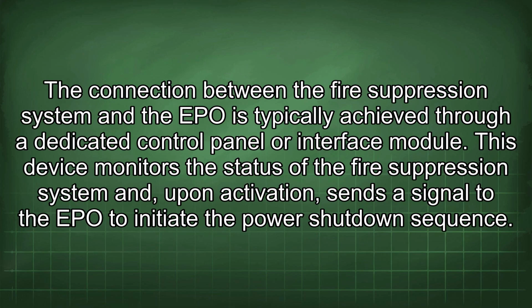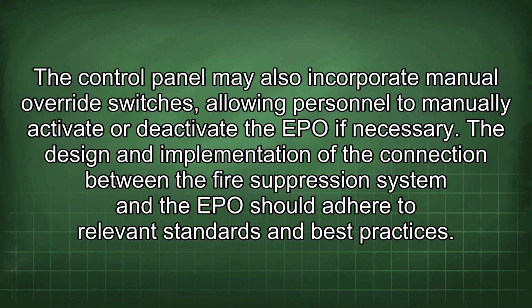The connection between the fire suppression system and the EPO is typically achieved through a dedicated control panel or interface module. This device monitors the status of the fire suppression system and, upon activation, sends a signal to the EPO to initiate the power shutdown sequence. The control panel may also incorporate manual override switches, allowing personnel to manually activate or deactivate the EPO if necessary.